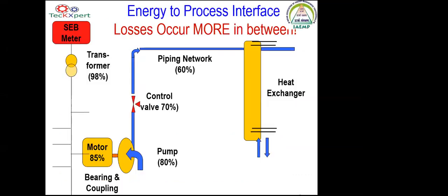So each and every industry, maybe an MSME, a medium scale or a large scale industry, has energy losses happening in individual energy equipment. Like a transformer: you assume it's around 99.5% as stated by the OEM as per the 1180 standards, but the efficiency is only around 98%. Motors: the average motor efficiency is around 85%. So from the transformer to the motor to the pump to the control valves to the piping network to the process, almost only 30% of the real energy goes to the process.